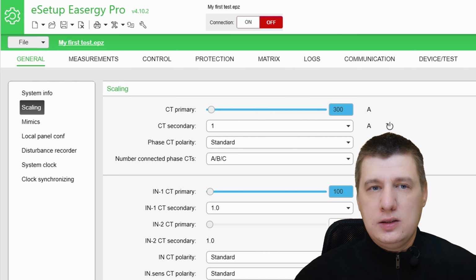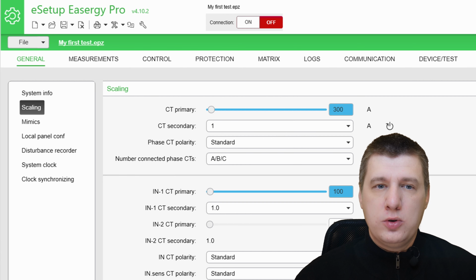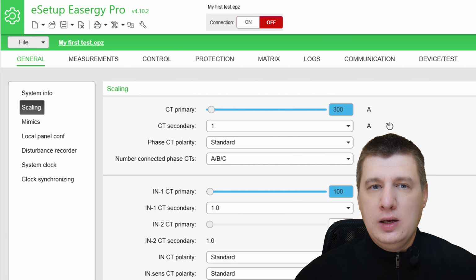Secondary scaling is input signals. This refers to the physical signals actually injected in the relay's rear connectors. These are typically 1 amp or 5 amp for current and 75 volts or 200 volts for voltage. These use specific voltage references such as 22.5 millivolts for current sensors.